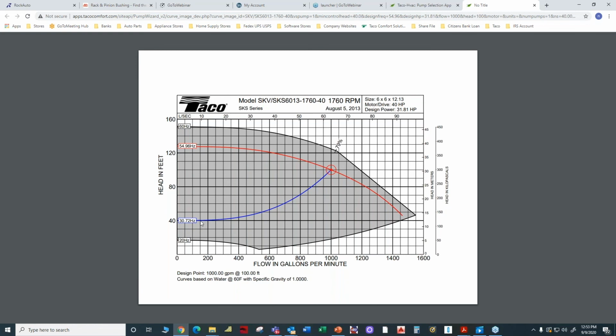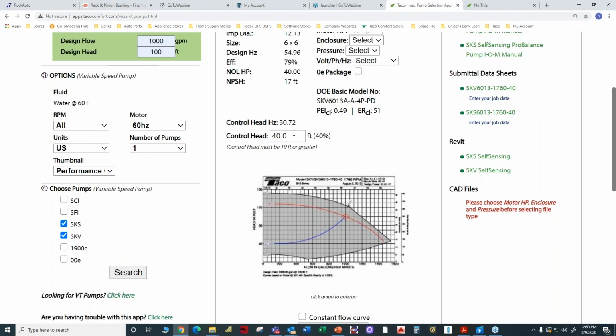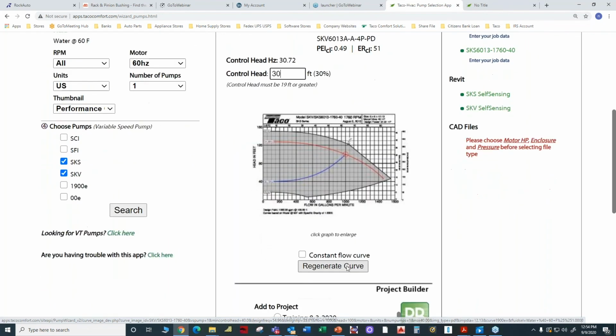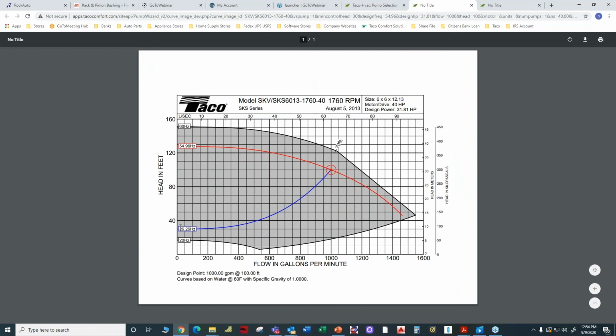So if I calculated what the actual pressure drop would be at minimum flow, if I was extremely accurate, my pressure differential at minimum flow is not going to be 40 feet. It's actually going to be 30 feet. So it's roughly 150 gallons per minute at 30 feet, which is the same as the control head. So I can go back here and put this in at 30 feet, and it's going to regenerate the curve.